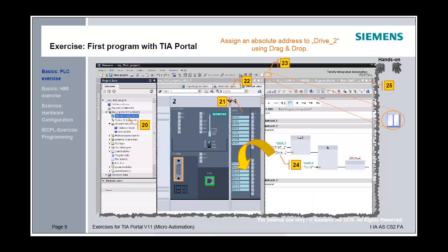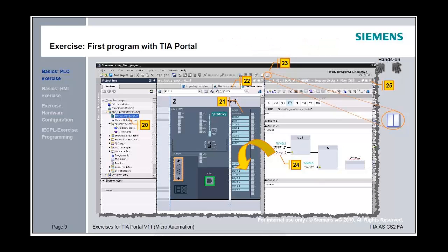Open the device view by clicking on device configuration. This shows the control module hosting the IM 151-8 PN/DP module. From the hardware catalog, change the zoom to 100%. In the working area, assign the absolute output address Q0.2 to Drive 2.